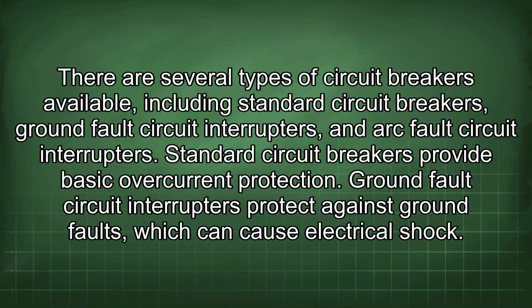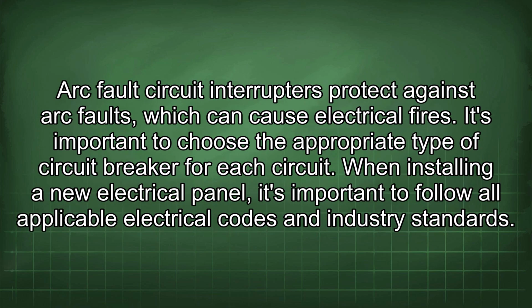interrupters. Standard circuit breakers provide basic overcurrent protection. Ground fault circuit interrupters protect against ground faults, which can cause electrical shock. Arc fault circuit interrupters protect against arc faults, which can cause electrical fires. It's important to choose the appropriate type of circuit breaker for each circuit.